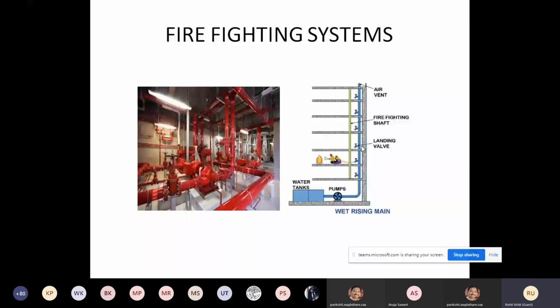I'm sure that all of you have seen both these things, and all of you must have wondered why there are two separate types of firefighting systems on every floor. So this is the primary reason. The one is for the use of trained fire personnel, and the other one is for the use of the general public who are occupying that space. The water supply line goes directly up to the terrace and can be connected to an overhead firefighting tank if that is demanded by codes, or it terminates at an air vent at the roof level.